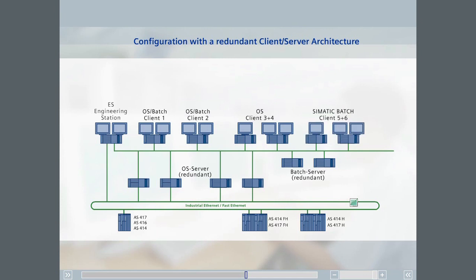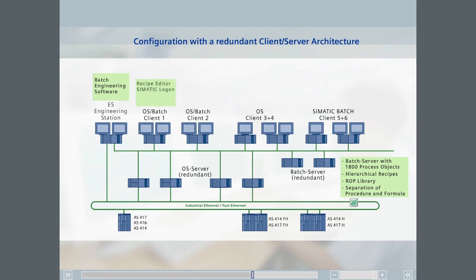The combined OS and batch clients from the previous example are extended by two OS clients without batch and two batch clients without OS. The batch engineering software is once again installed on the engineering station. The two redundant batch server PCs both have the server software and the options hierarchical recipes, ROP library, and the separation of procedure and formula installed on them. The recipes will be created on client one, which therefore has the recipe editor and SIMATIC Logon, but is without a batch control center.